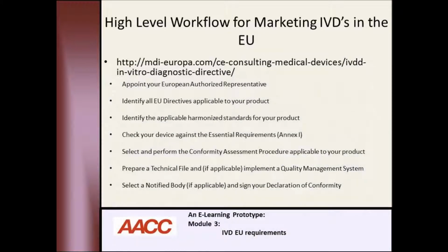Before we get to the IVDD, let me present some high-level workflow steps associated with any effort to get an IVD to market in the European Union. These steps are provided in no specific order. In fact, the order might differ depending upon the situation and the product, but they include appointing an authorized representative, identifying all directives and standards that apply to your product, checking the device against the essential requirements found in the IVDD, performing the appropriate conformity assessment procedure as needed, preparing your technical file, and then working with your notified body to sign your declaration of conformity.